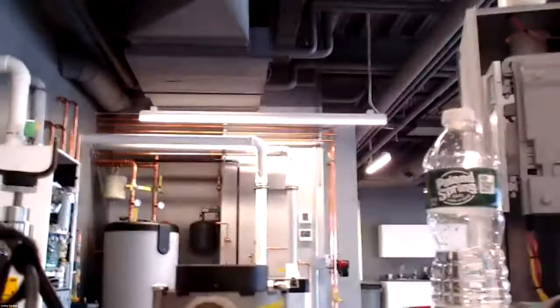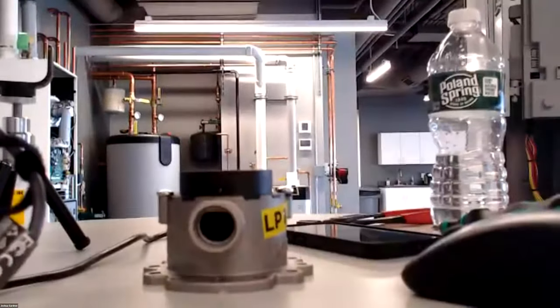Working down on the return side, with the flashlight in here, we have our flow sensor, which is this guy right down here. So we have a wire lead on it, and we have a little C-clip. You pull that C-clip up, and our flow sensor pulls right out of there. So I'll show you what that looks like.